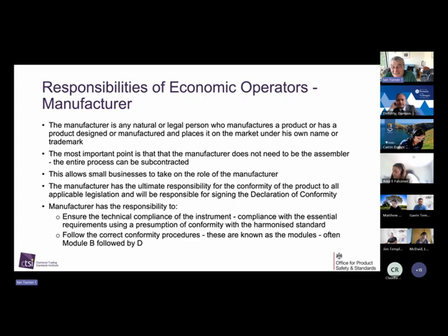The second one is the thing we don't really spend much time enforcing in market surveillance: follow the correct conformity assessment procedures. They're legal obligations. I have to ensure the instrument complies with essential requirements and use the correct conformity assessment procedures to get it there. So if I have an instrument that hasn't had, back to our airport wires, a proper Module D process or a Module F process, where both parts have correct certification but the entire compliant instrument doesn't have the correct certification, I have a non-compliant instrument. And it's as non-compliant as if it didn't weigh correctly. The reason that's important is the distortion of the market. It's trading standards issues. What we're dealing with here is a cost base, and some companies working at different cost bases. So that's why both of those are important.